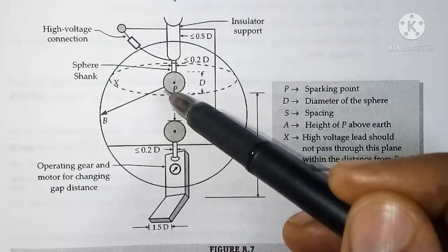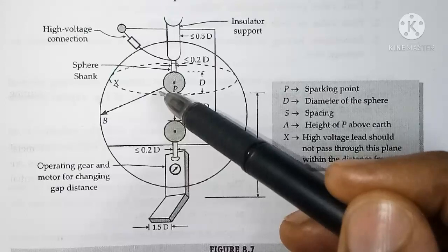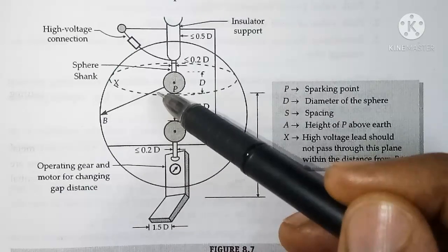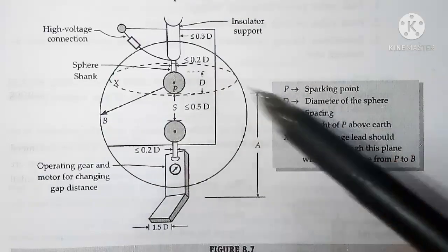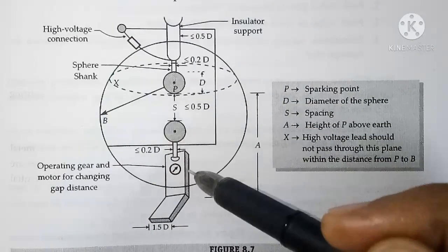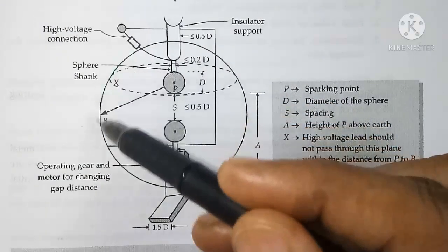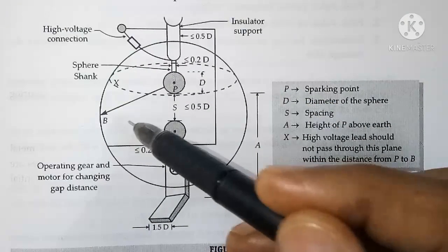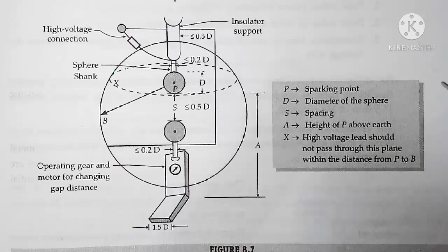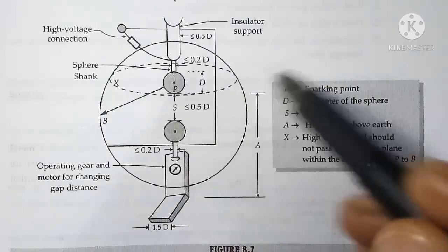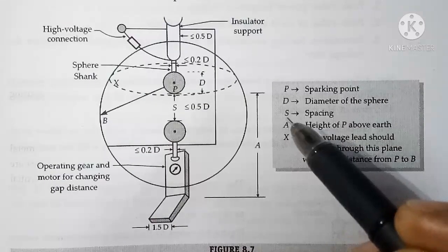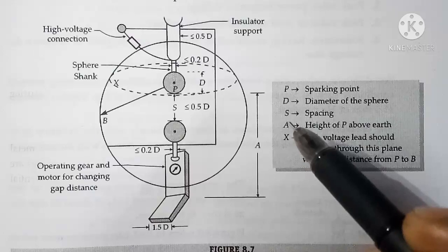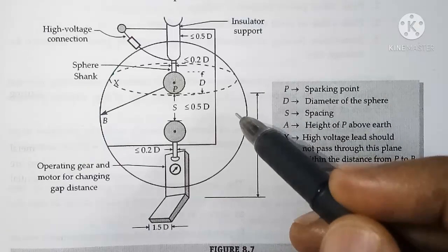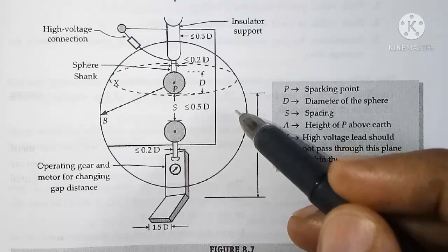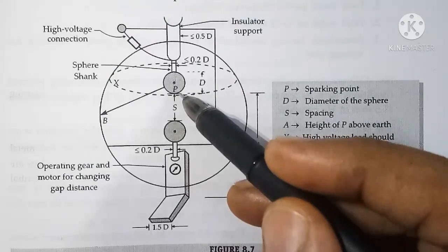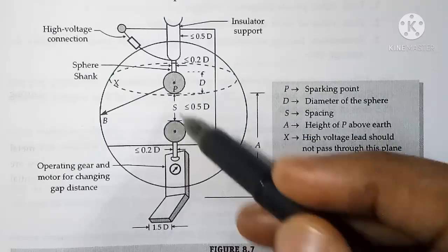Here you can see radius B, and this radius B is of a sphere around the two small spheres, and that spear having diameter of B is called the clearance spear. Within this clearance spear there should not be any earthed objects, because if any object comes within this sphere then it will have an effect on the breakdown voltage of this spark gap.